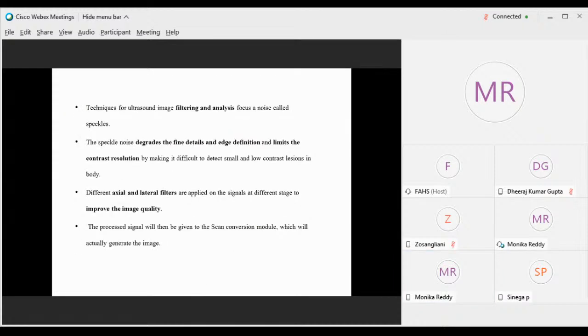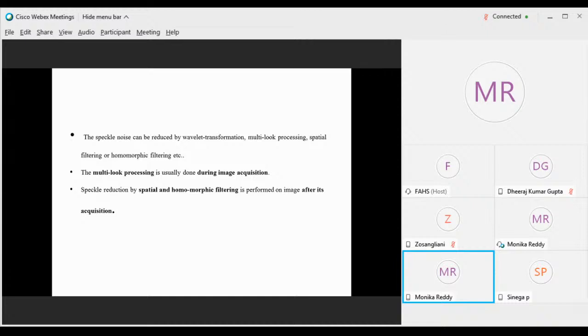Techniques for ultrasound image filtering and analysis focus on noise called speckle. This speckle noise degrades the fine details and edge definition and limits the contrast resolution. Different axial and lateral filters are applied on the signals at different stages to improve the image quality. This processed signal is then given to the scan conversion module, which will generate the image after the post-processing. The speckle noise can be reduced by wavelet transformation, multi-look processing, spatial filtering, or homomorphic filtering. Multi-look processing is usually done during the image acquisition, and speckle reduction by spatial and homomorphic filtering is performed after the image acquisition.